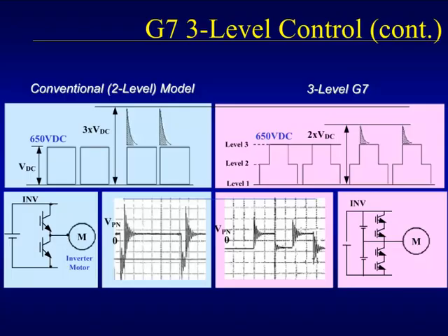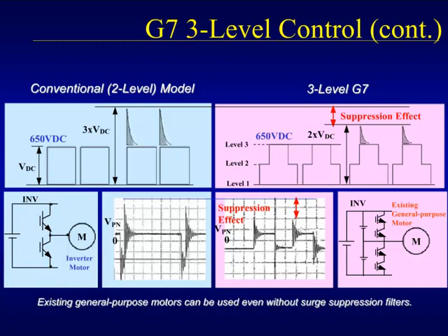The graphics on this slide demonstrate the theoretical beneficial effects of 3-level output. With a conventional 2-level output, the motor terminals may see voltage peaks 3 times the amplitude of the DC bus. But by using the 3-level control, a suppression effect can limit the voltage measured at the motor terminals to only twice the amplitude of the DC bus. The clear benefit of using the G7 is that motors with weaker insulation, such as general-purpose motors, will survive much longer without insulation failures when driven by a G7.